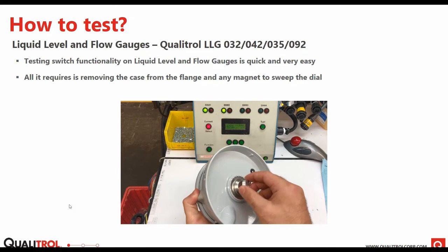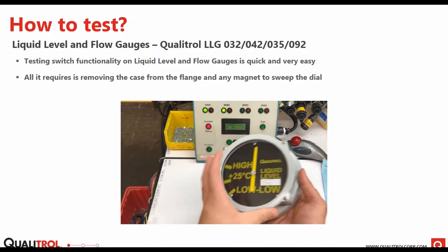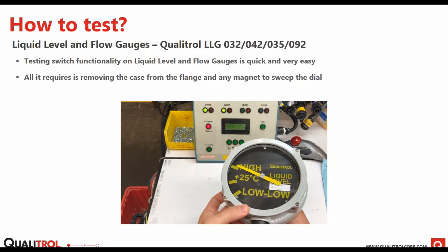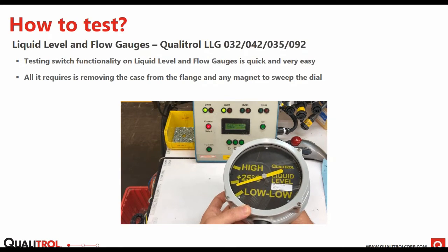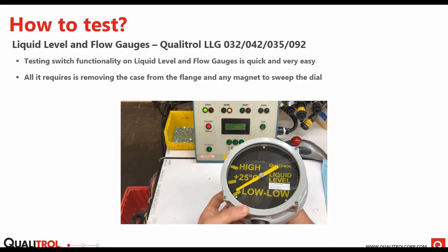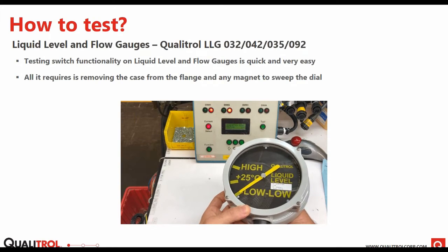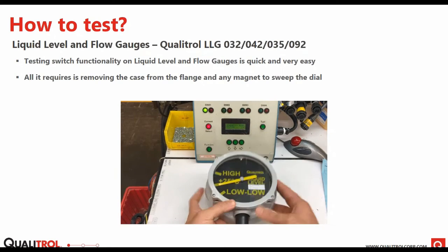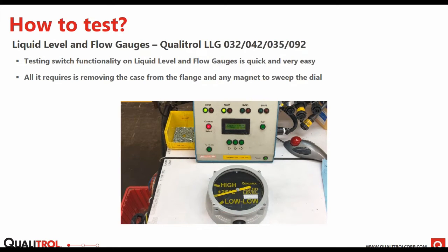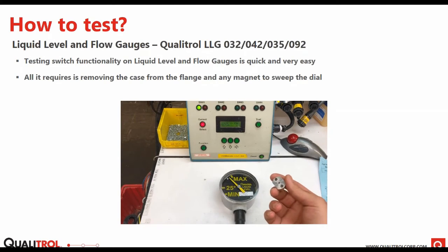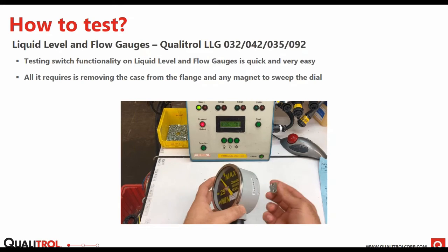and then use any magnet, and you can place that right on the center back of the drive shaft of the liquid level gauge, and you can actually move the pointer and actuate the switches. So here you can see there's the first low switch and there's the second low switch. And all I'm doing is twisting that magnet on the back. And that gives a good simulation of the actual drive mechanism moving inside the tank. And then the same on the 3.5-inch liquid level gauges as well.